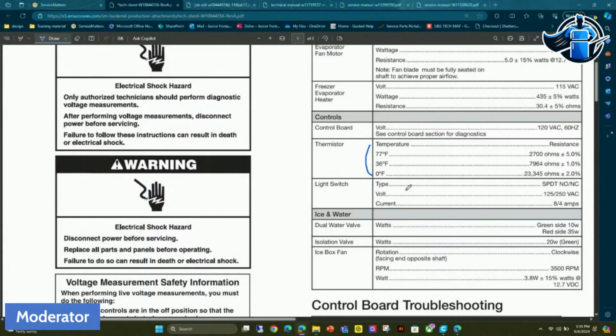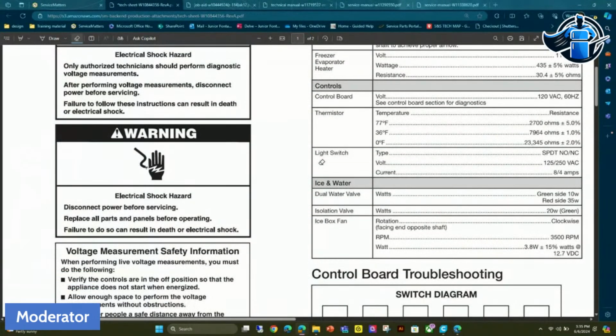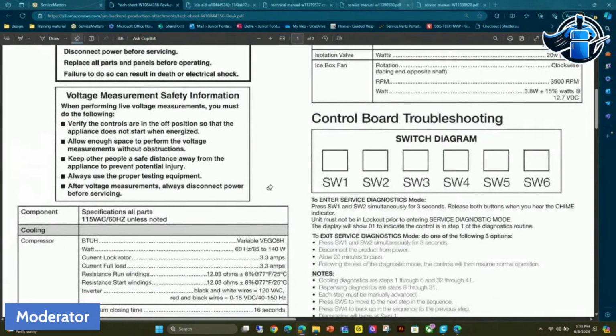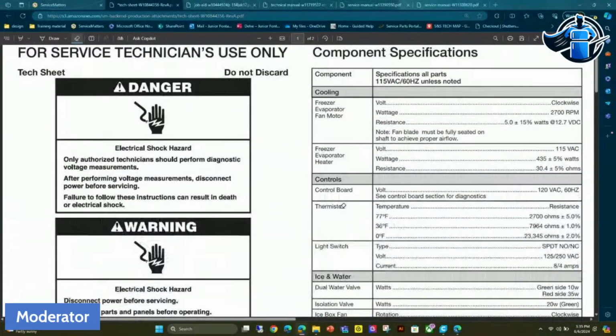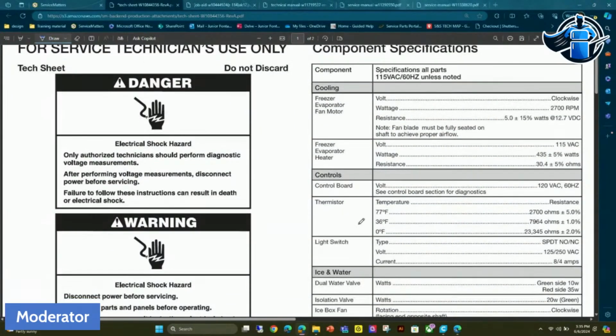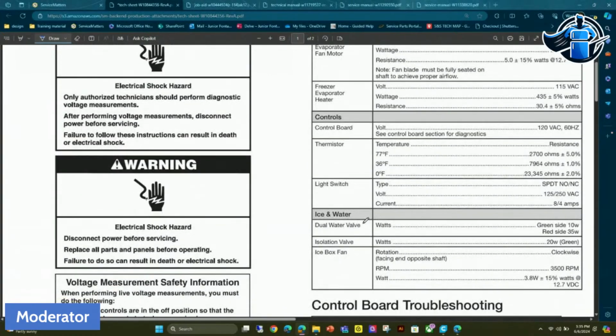Even thermistor values. Now, I know Whirlpool is not too friendly when it comes to thermistor values. They typically only share 3 temperatures: room temperature, 36 to 32 degrees, and 0. That's basically all you will see usually on Whirlpool units, not saying all of them, but for the majority. It's going to give you current, voltage, wattages for different components.